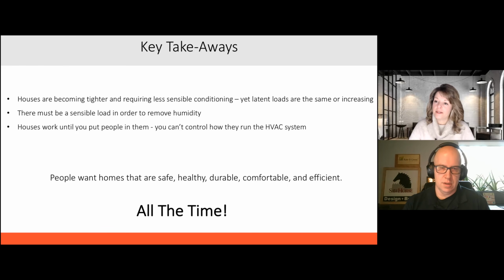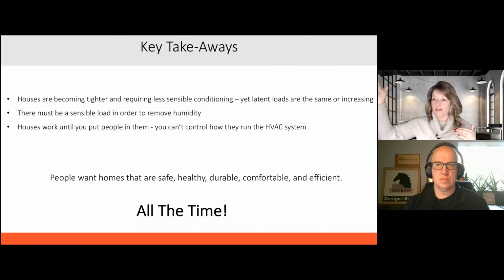Like, how does your system integrate with the whole house, you know, balancing it out? So, we are more about, when we are ventilating, trying to put that positive pressure. So if you're exhausting in the bathroom, 50 CFM, and it's not time to ventilate with the dehumidifier, because we're going to ventilate set up on a time schedule, then you're probably going to be off balance for a little bit. But as soon as that shuts off, then the dehumidifier, when it's time to ventilate, is going to come in and put that positive pressure back on.